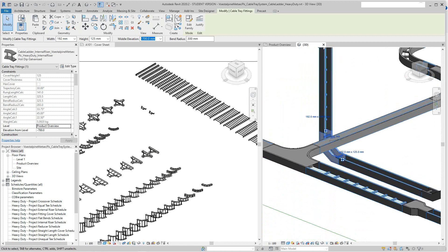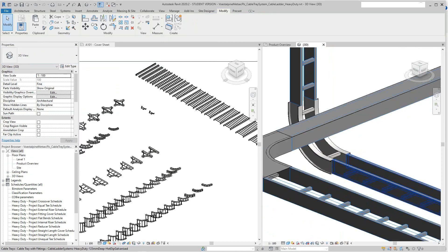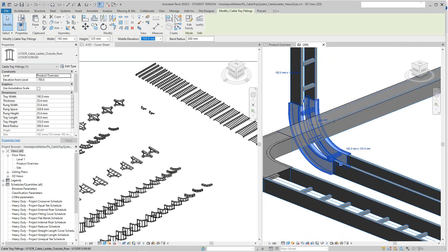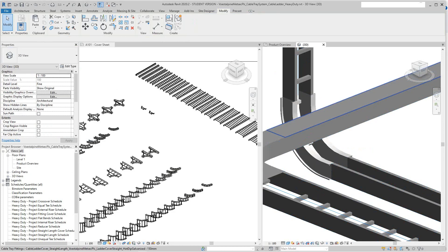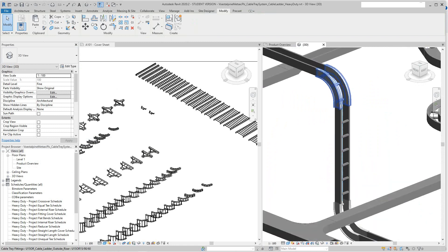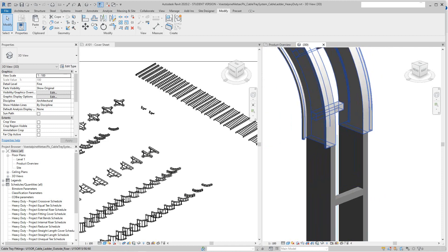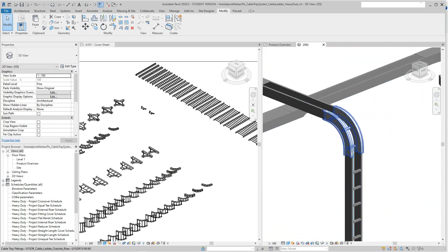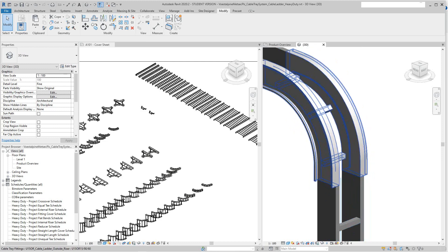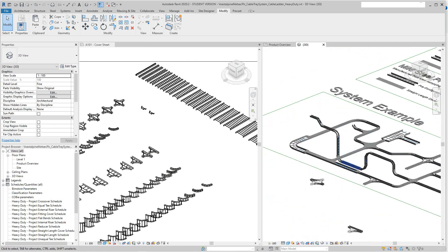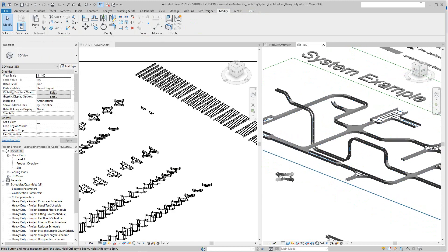This is all what he means when he swaps out — he probably doesn't care about anything but doing this, because I think you mentioned they're swapping old to new. So look, that's wrong — that should be this one. That's the correct tray fitting that should go there. It's more important to cover the inside. We do prefab here at CNC where we need to know the exact sizes of the rungs, the depths, and the height — more detail — that's what we use.